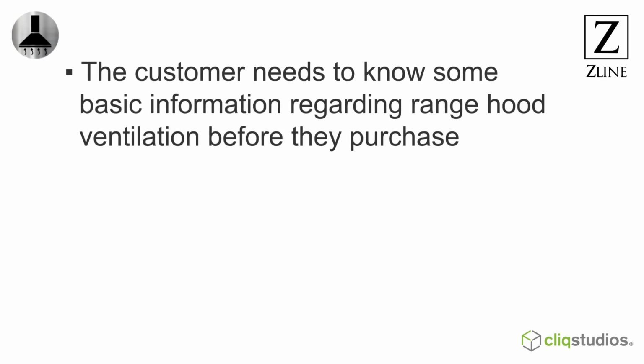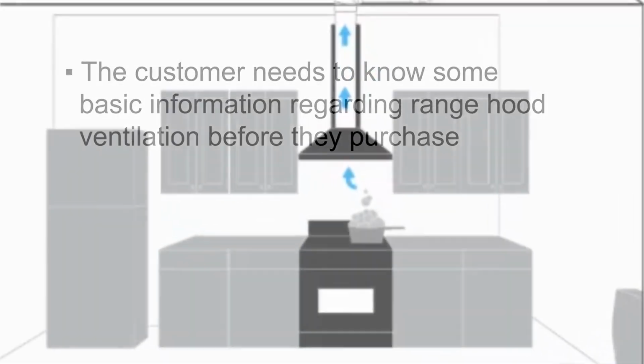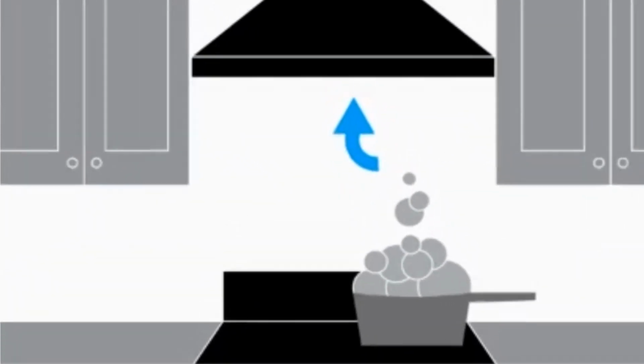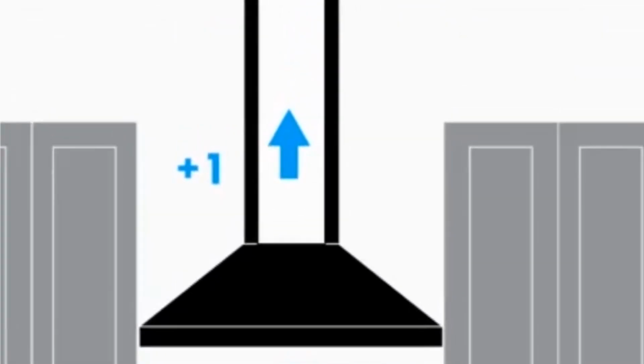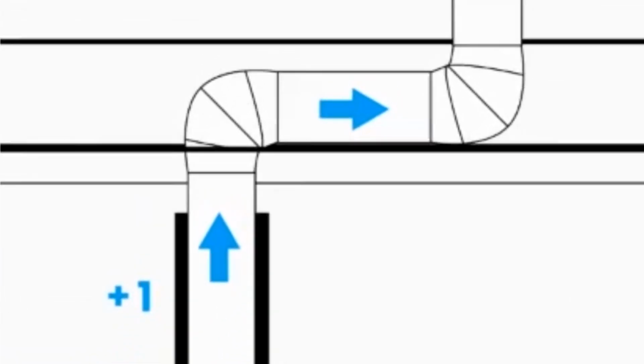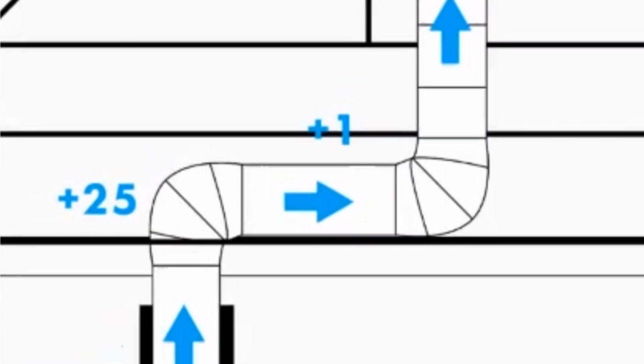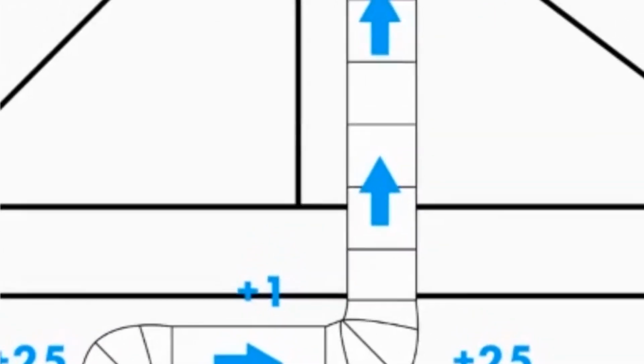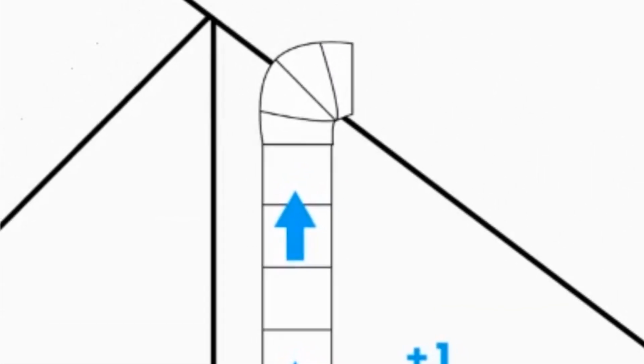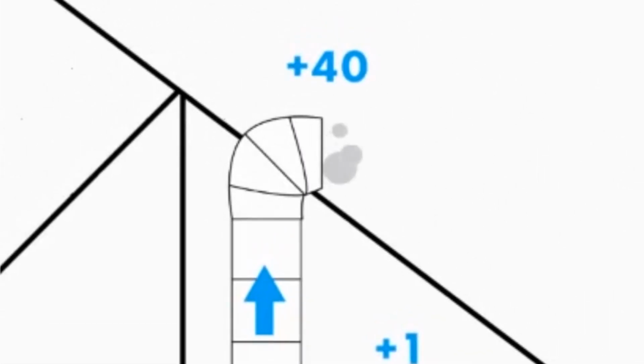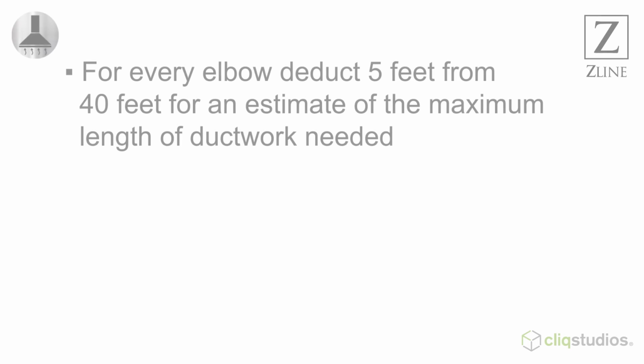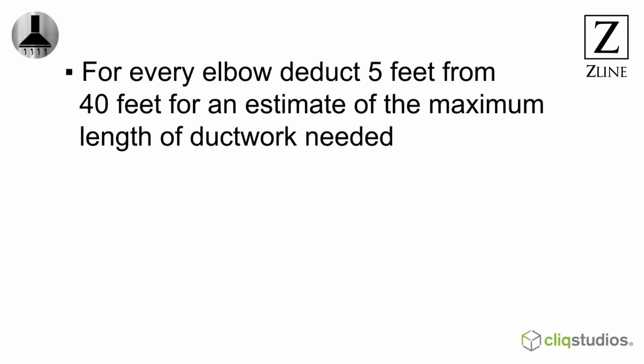Even if a customer is not a DIYer, they still need some basic information regarding range hood ventilation to make a purchase. If the range hood is to be vented to the outside, ducting pipe material is used to channel the air from the hood to the outdoors. Typically, you don't want more than 40 feet of ducting from the hood to the exit. Ductwork can add an additional 1 CFM per foot, 25 CFM per elbow, and 40 CFM for a roof cap. For every elbow, deduct 5 feet from 40 feet for an estimate of the maximum length of ductwork needed.